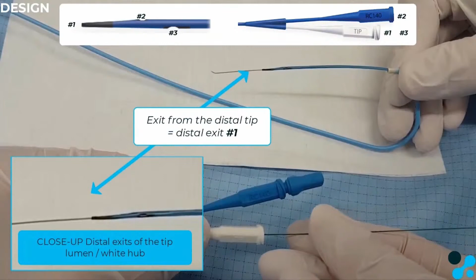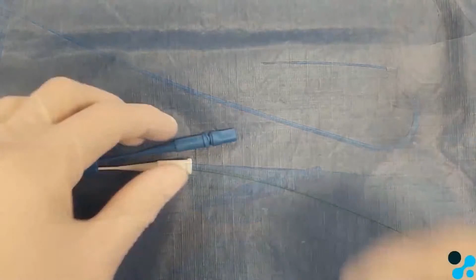The white hub is connected to the tip and to an additional exit port number 3. So the white hub, which is mentioning tip, is connected to both the tip and the proximal exit port. The guide wire should always be slightly shaped, and depending on the rotation of the guide wire at the proximal end, it will come out of either the tip or the proximal exit port.